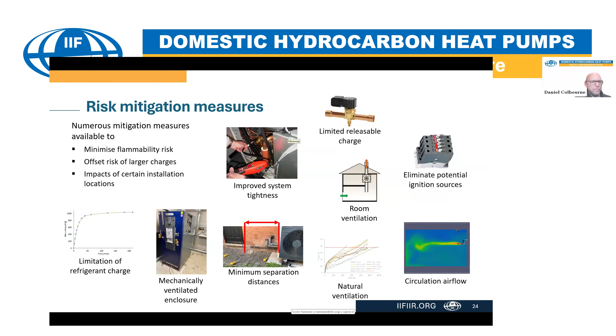Natural ventilation, of course, particularly for heat pumps that are located outside. There are minimum separation distances to avoid access or gas flowing into parts of the building. There's a mechanically ventilated enclosure option, where the whole refrigeration system is inside the enclosure, and there is an extract ventilation to exhaust the leaked refrigerant to the outside. And then of course there's the limitation on refrigerant charge as well, which may be related to the room size, or it may be applied to an overall cap limit for systems.